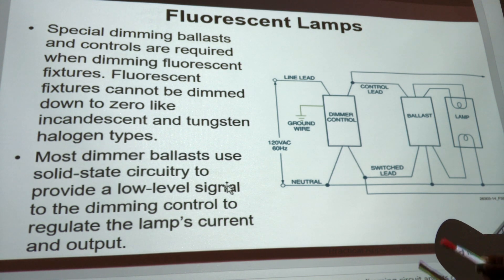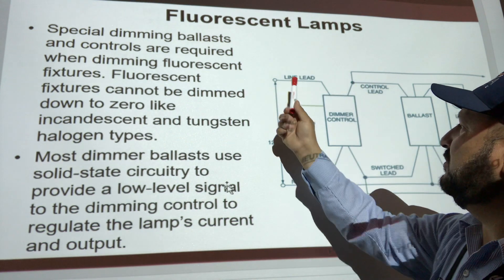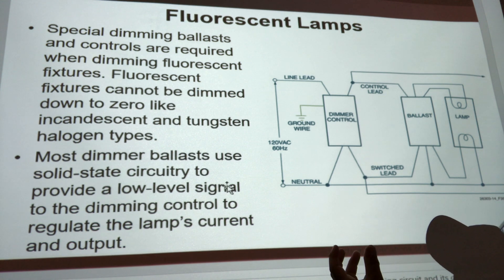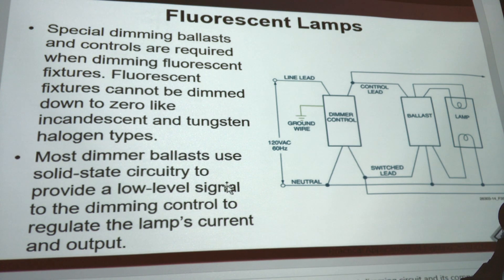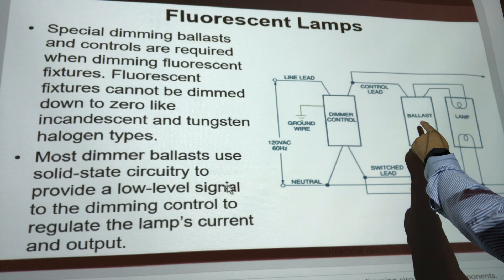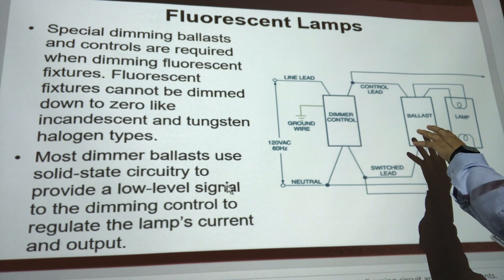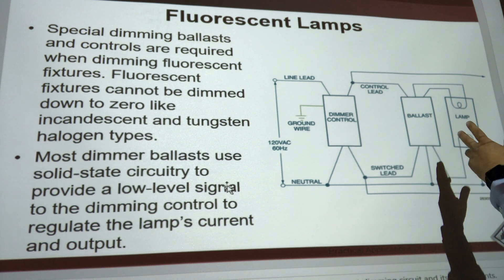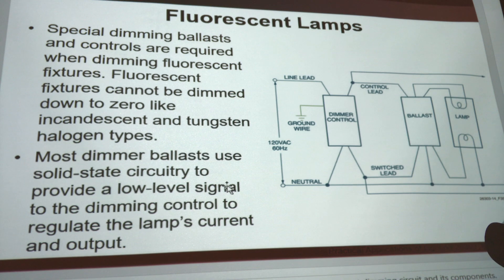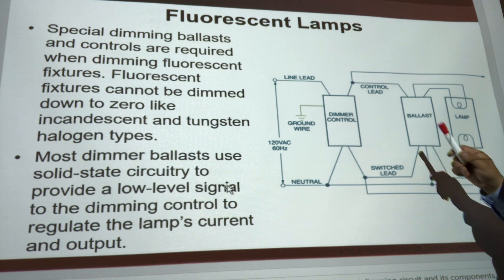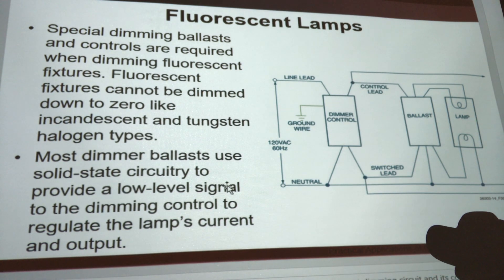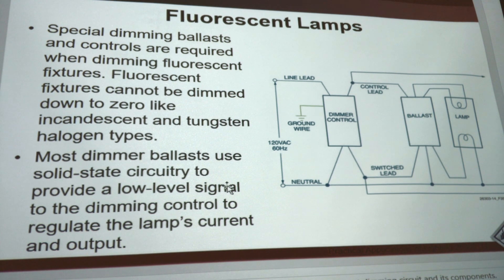Fluorescent lights can be controlled — there are special ballasts and special dimmer switches designed for fluorescent lighting. The ballast controls the lamp, so you need special dimmers to control the ballast to control the light and dim it. Nowadays we're getting away from fluorescence. We're showing you fluorescence so you know what it is when you run into it, but as these phase out, we're going to LED systems controlled with Cat 5 or Cat 6 cable.